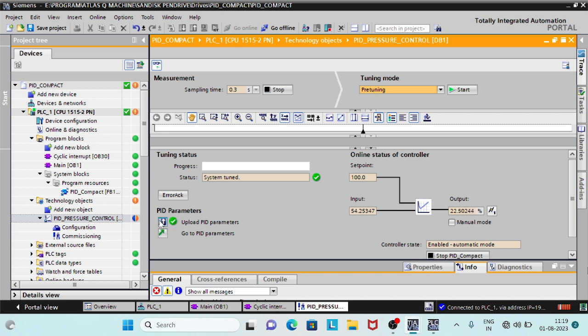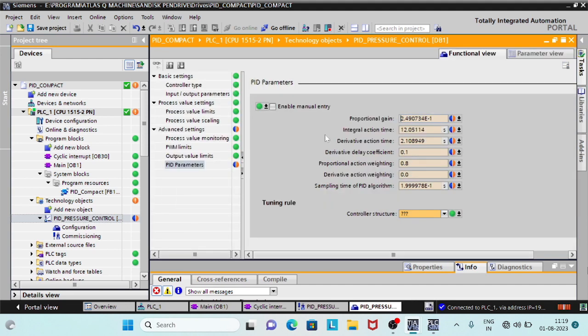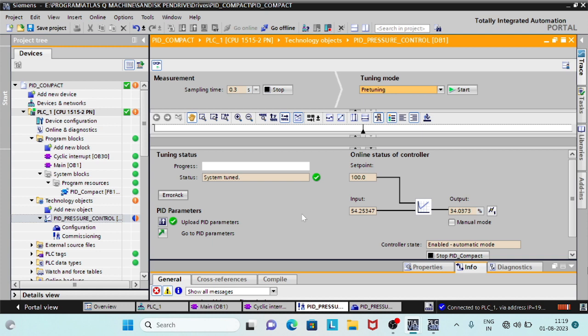On clicking Upload PID Parameters, the updated values are written to the project in the instance data block of the PID Compact. After pre-tuning is completed, you can view the updated PID parameters by clicking on Go to PID Parameters. Use the Manual Mode button to manually set the output value.